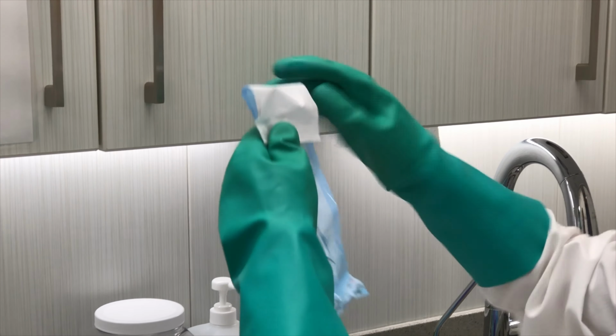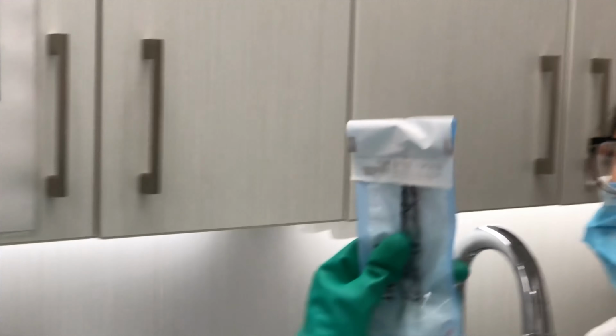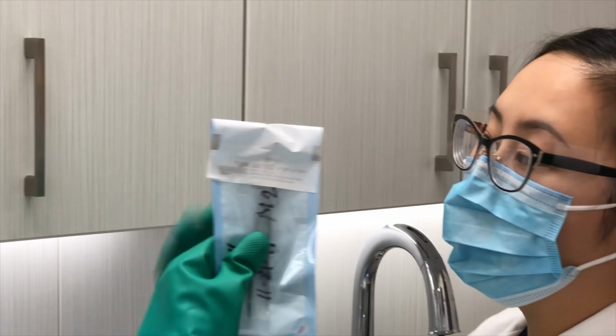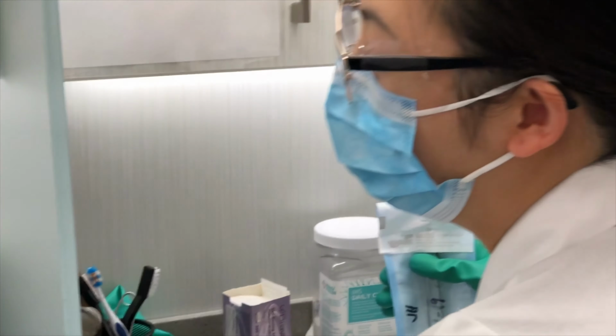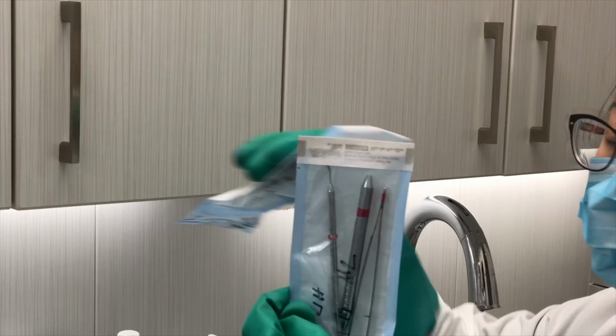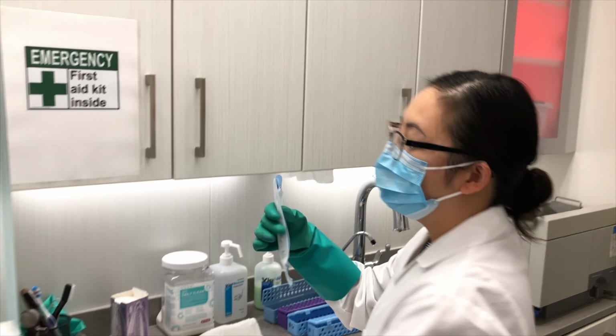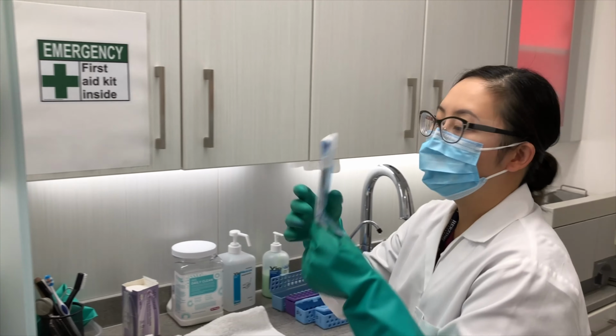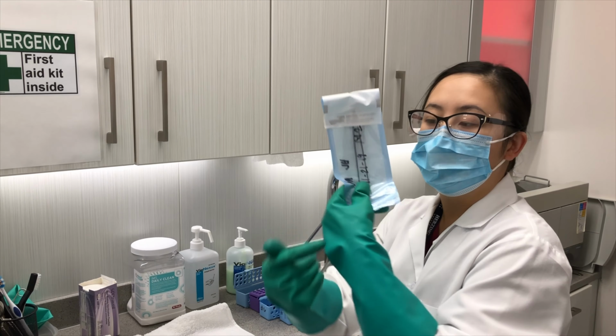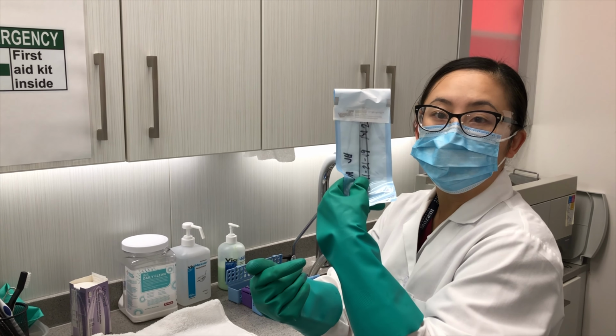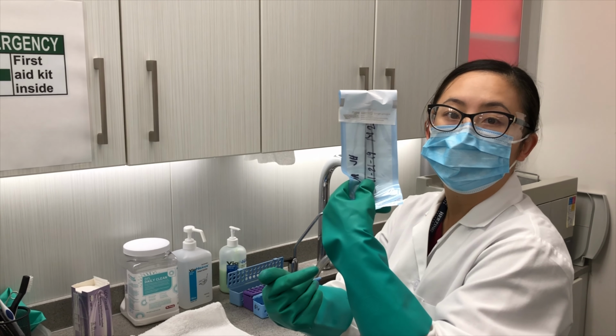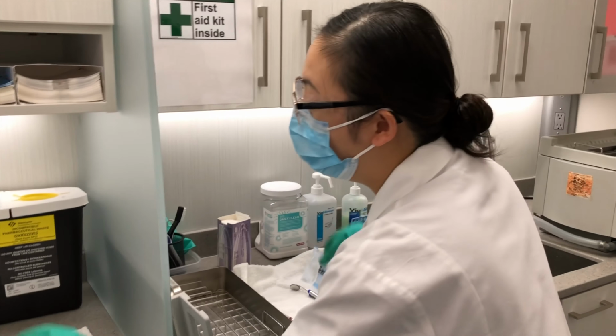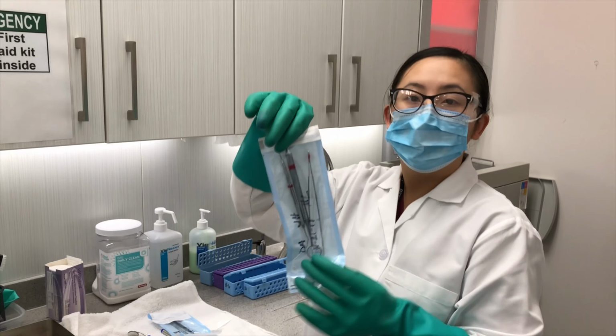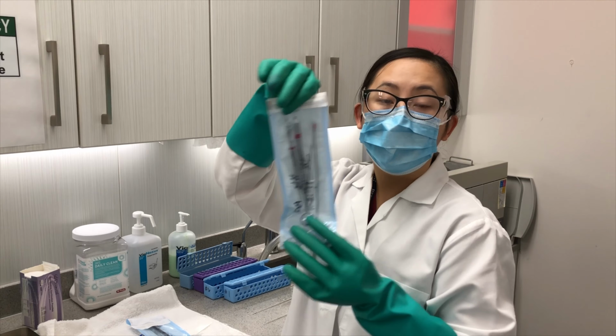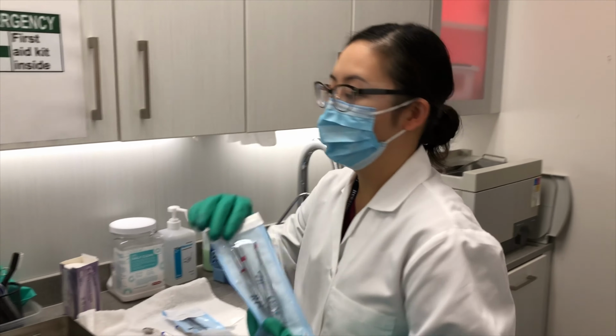You should not seal the pouches like this. The instruments are not considered sterile even if they pass the 3 sterilization monitoring methods. They should be sealed like this, along the perforated line. If the pouches are sealed properly and passed all 3 sterilization monitoring methods, which are physical, chemical, and biological, these instruments inside the pouches are sterile indefinitely until it's opened.